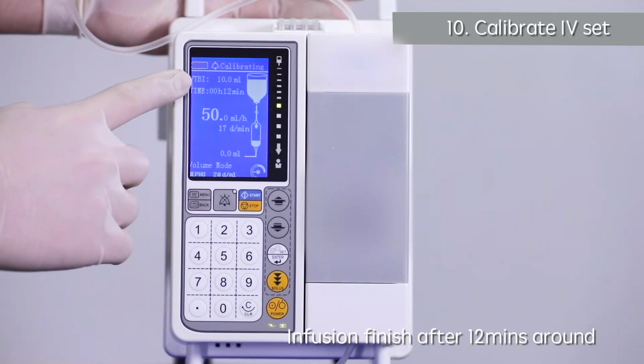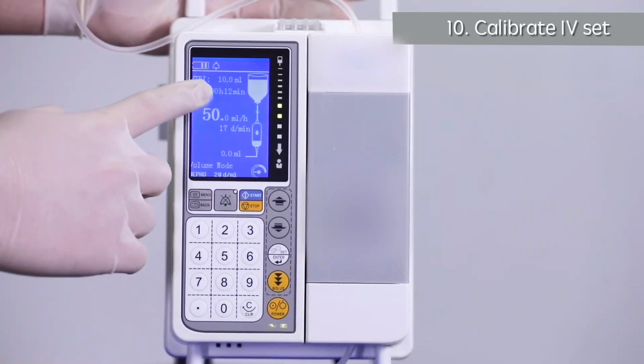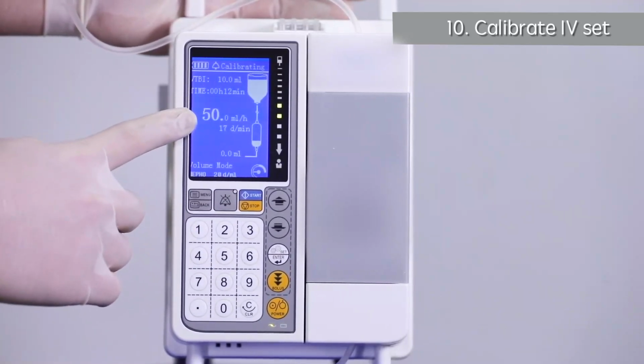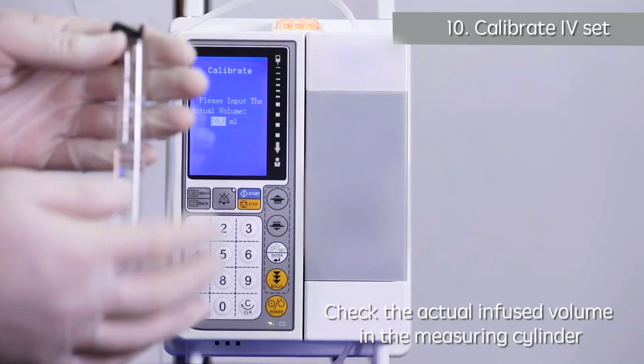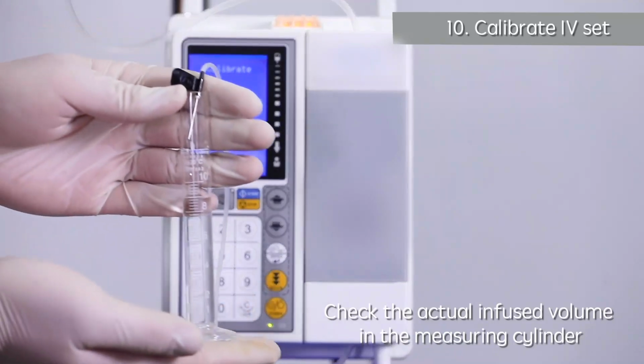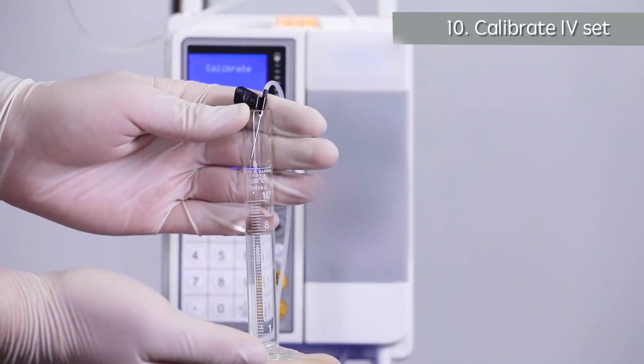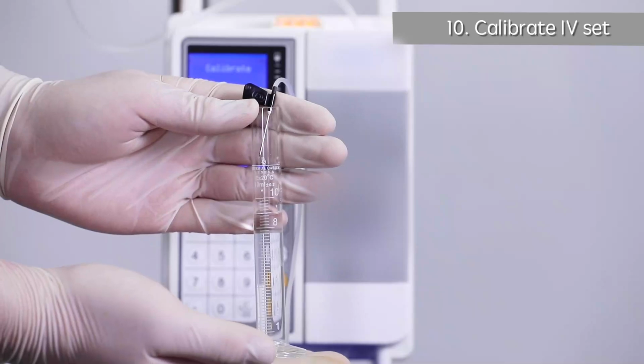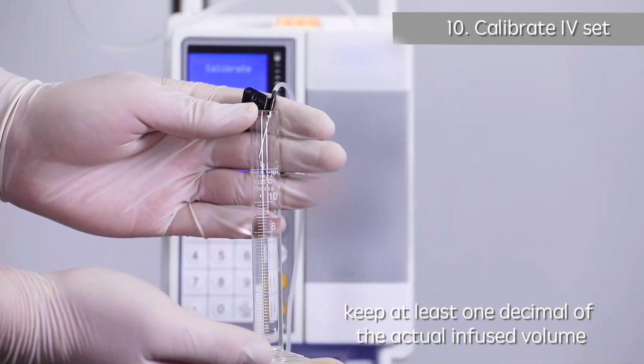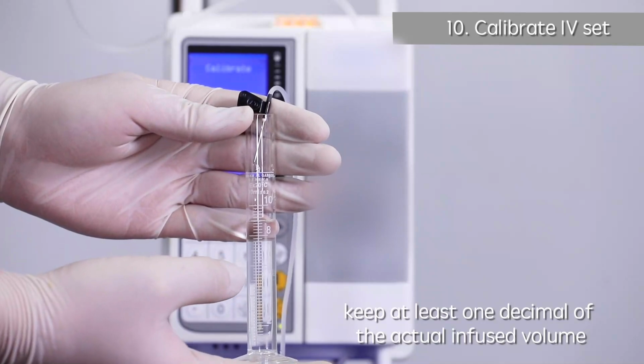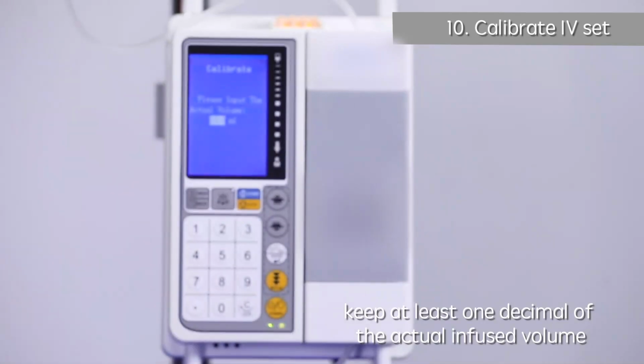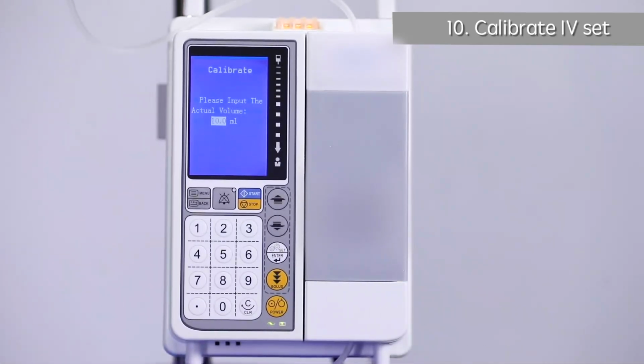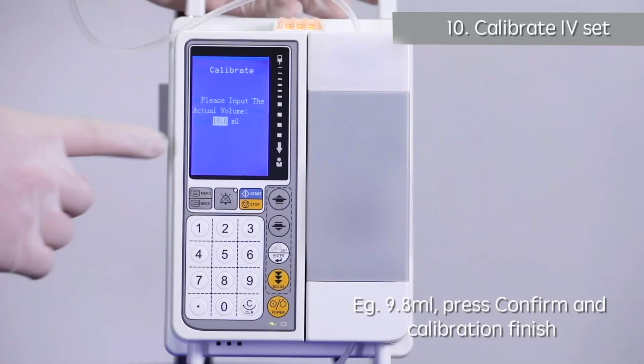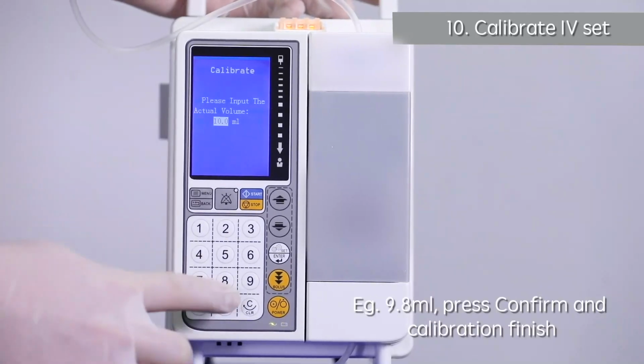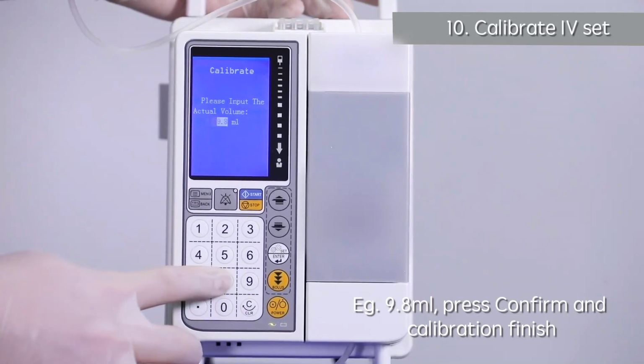Infusion finishes after around 12 minutes. Check the actual infused volume in the measuring cylinder. Keep at least 1 decimal of the actual infused volume, for example 9.8 ml. Press Confirm and calibration finishes.